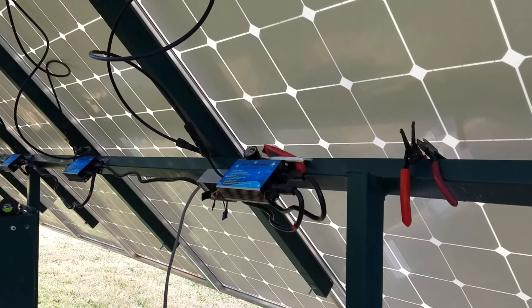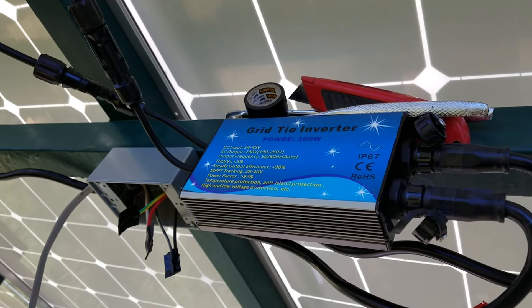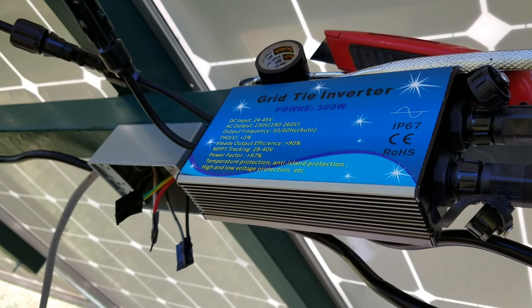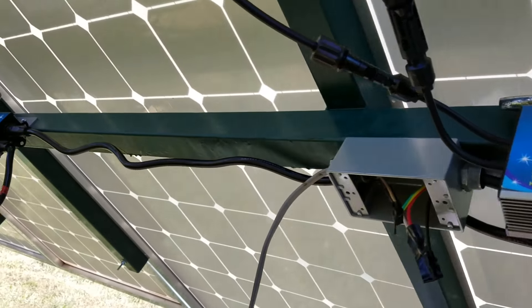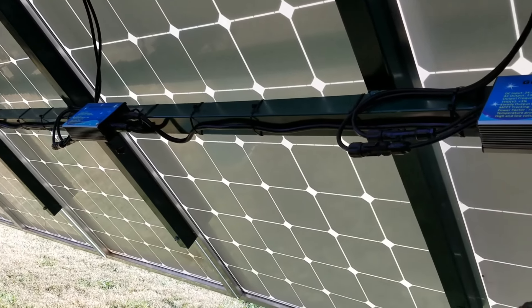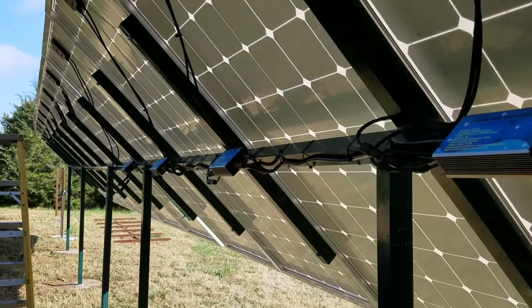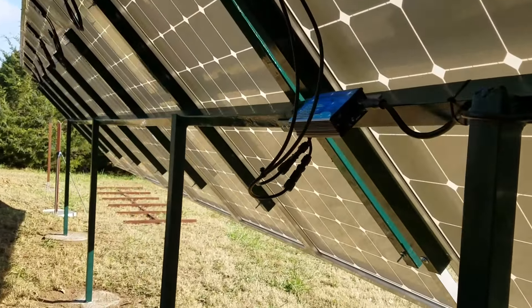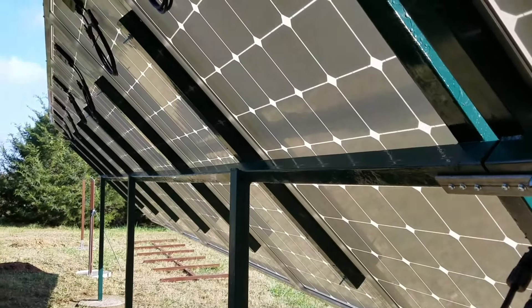Looking here on the backside of the panels, you can see that he has modified the inverter mounting from what it was. This inverter mounting seems to work much better as far as heat dissipation. Right now there are 8 inverters that he currently has wired up, and he's got a few more to go.